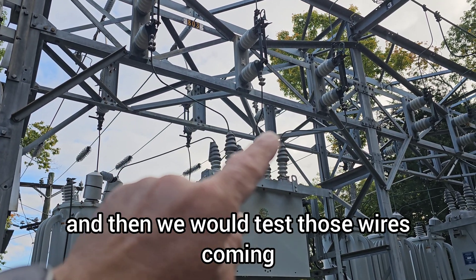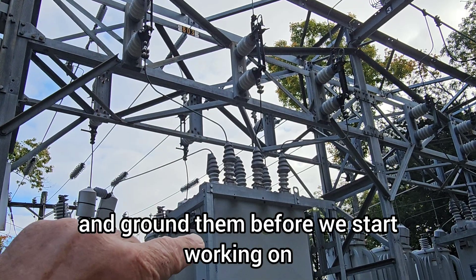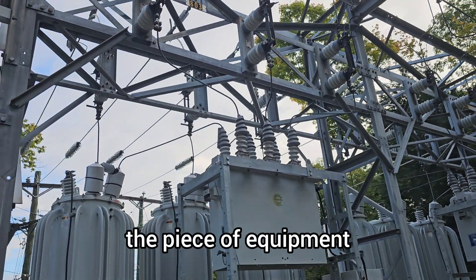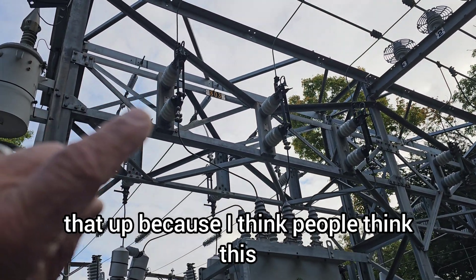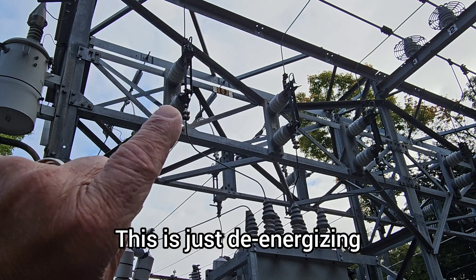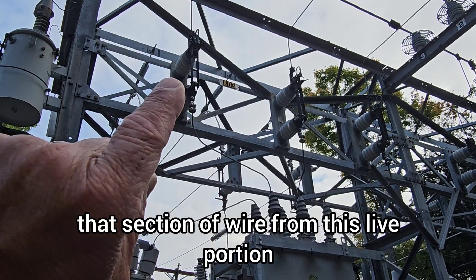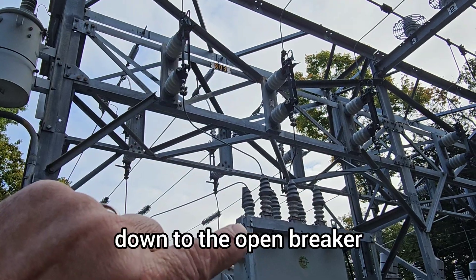Then we would test those wires coming down after this has been opened and ground them before we start working on the piece of equipment. I just wanted to clear that up, because I think people think this is actually breaking a load — but it isn't. This is just de-energizing that section of wire from the live portion down to the open breaker.